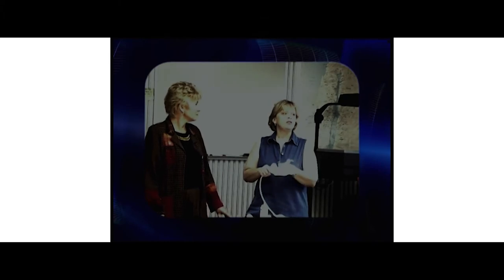Are the Cidex wipes as effective as soaking? Absolutely. The Cidex wipes, just like baby wipes, have to be marked in such a manner that people do not use them as face wipes or hand wipes. It's very critical that people understand that these wipes are for cleaning and have cleaning solution in them. But they are available and they are very effective, yes.